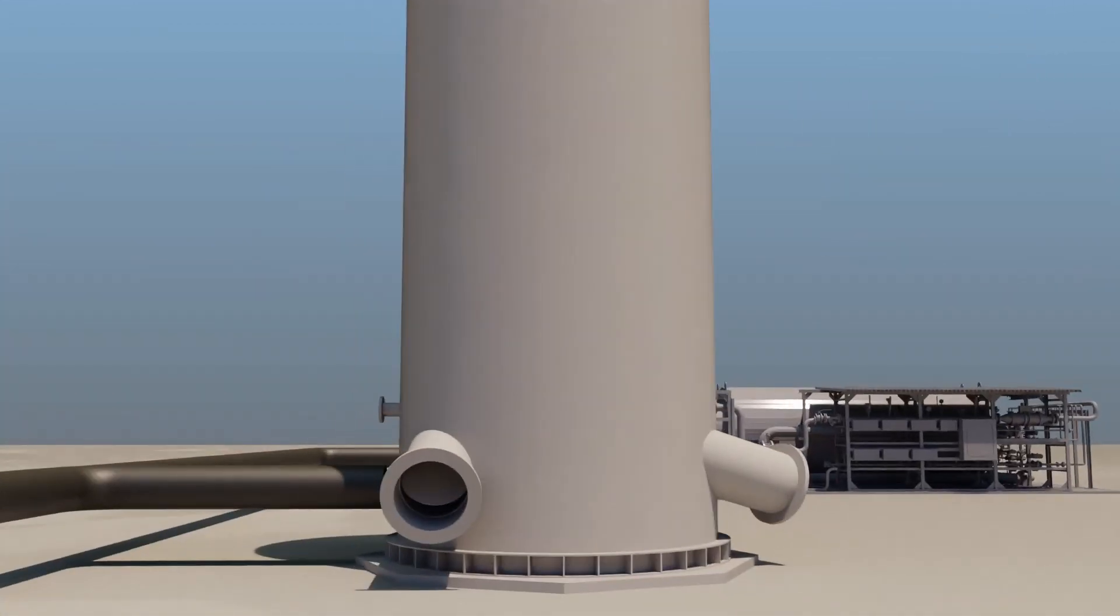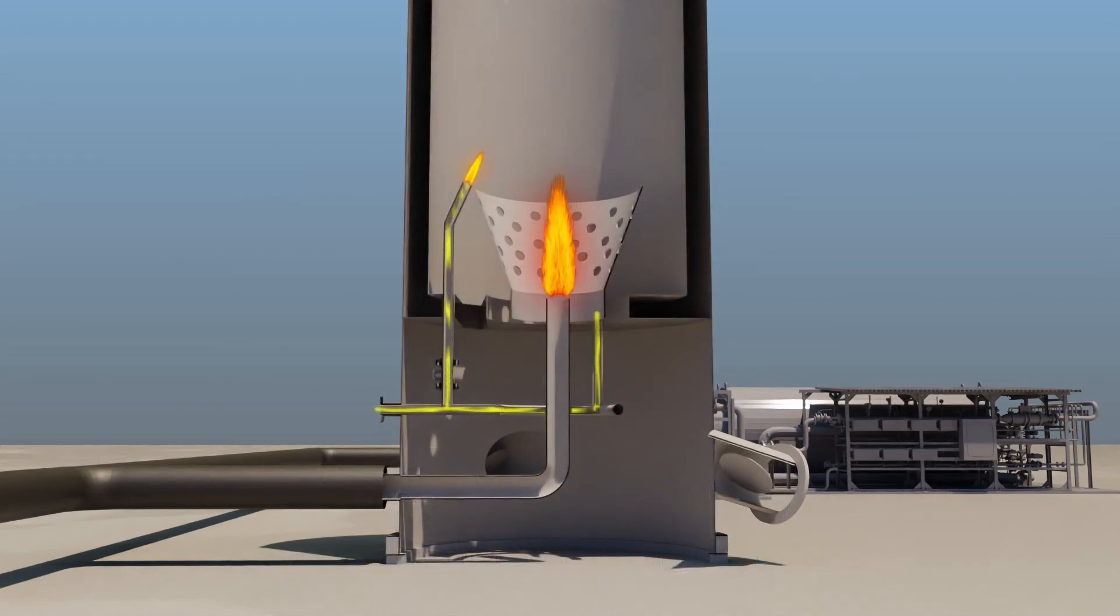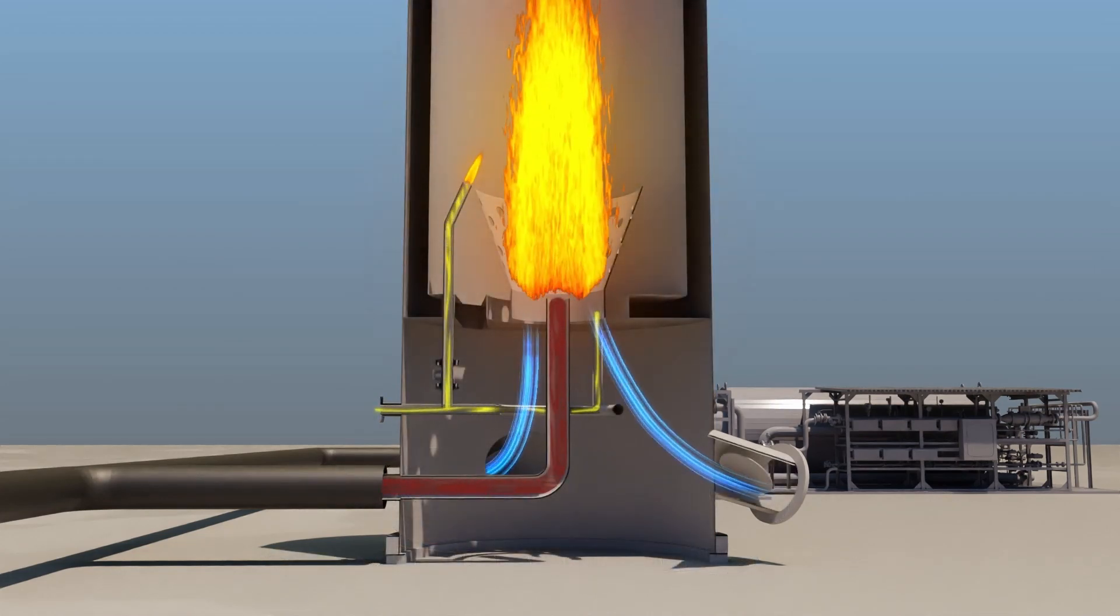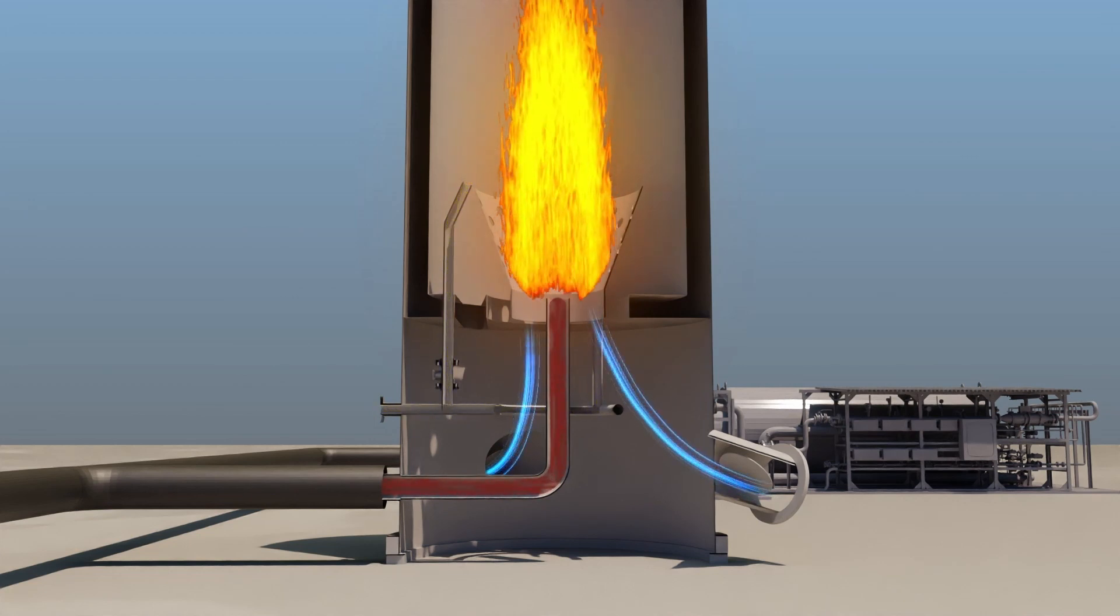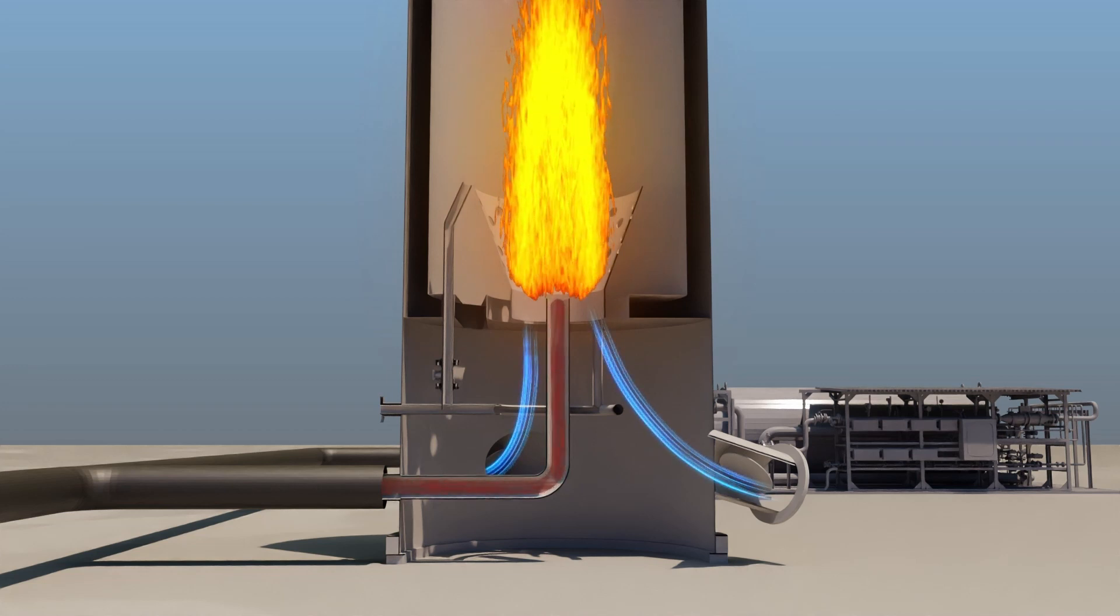In a conventional thermal oxidizer, the vapors are usually injected via a standard lance or flare system with fixed openings. If the vapor flow rate falls below a certain threshold, flashback of the flame becomes possible.